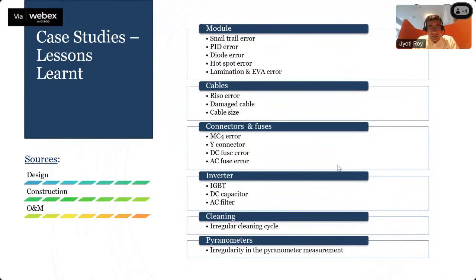Sometimes an inverter comes with some level of insulation resistance relay setting, and there's a range within which this insulation resistance operates. So check your OEM inverter manufacturer's recommendation for what range is given, and you can adjust the settings of your inverter to its maximum level. That may allow it to start earlier in the morning.